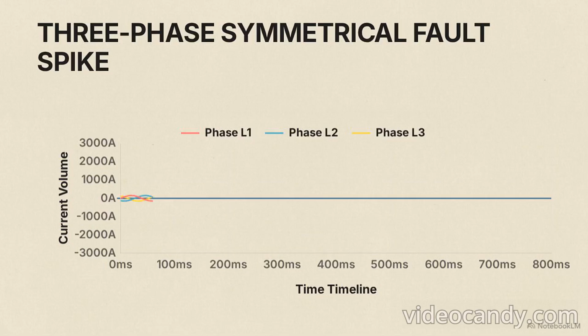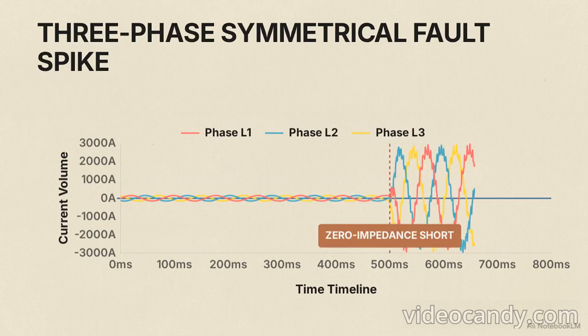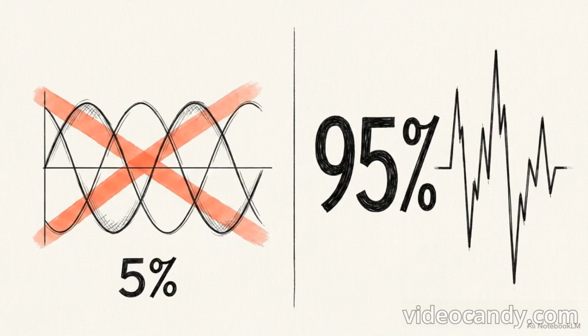The absolute highest potential fault a system can physically generate is a three-phase symmetrical fault. If all three active phase conductors make direct physical contact, the resulting zero-impedance dead short causes the current to instantly spike to thousands of amps. That balanced fault is incredibly destructive, but relatively rare.